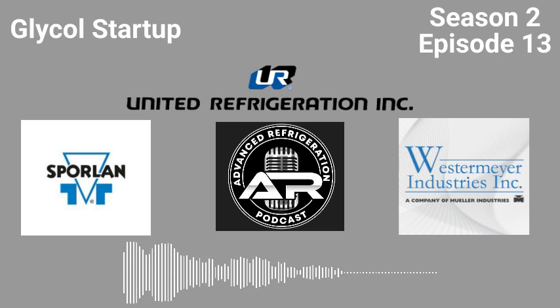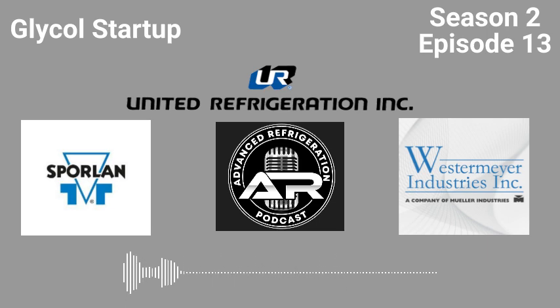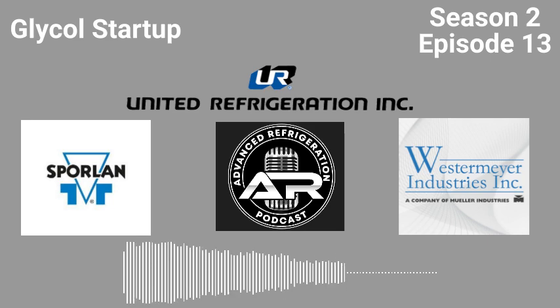Sporlan actually makes a glycol CDS valve, which I've yet to see in person, but to be honest, it looks pretty sweet. Does it look like the CO2 valves? Like the H. Yeah, it's got that big head on it. It would be great for case control, way better than solenoids. But at the same time, I don't know how much you'd be able to pinch down on it completely, because once you start pinching down too much, I would imagine it would affect the flow. Yeah, for sure. So I see why a lot of engineers and system designers aren't using those, because it is going to affect the flow.